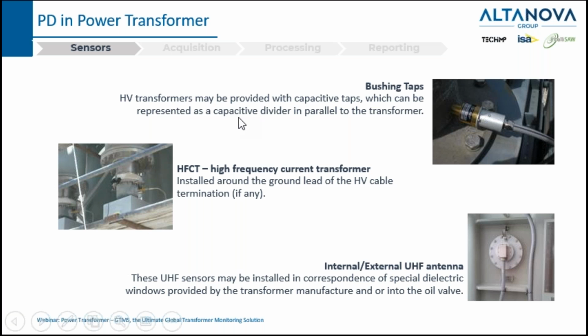We can also use a high frequency current transformer, HFCT, for example, installed around the ground lead of the high voltage cable connected to the transformer, when the bushing taps are not available on the bushings. This is a real example of the installation of the UHF antenna, which is normally installed at the dielectric windows that the transformer manufacturer is able to provide in the tank. There are other types of UHF sensor. Probably the most famous one is the UHF for the oil valve.